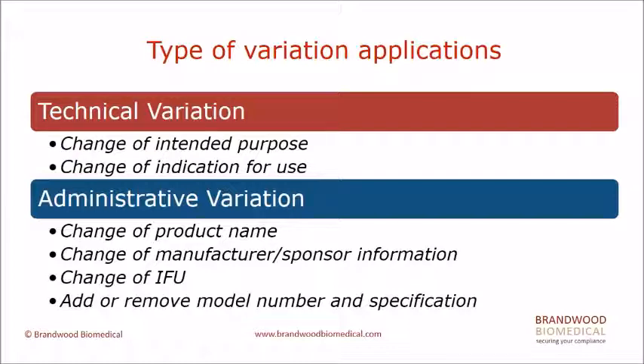The second type of variation is administrative variations: change of the product name, change of the manufacturer or sponsor information, change of the instruction for use, and adding or removing model numbers and specifications. Depending on the nature of the variation, there may be documents or reports requested during the review process. For example, if adding model numbers and specifications, the preclinical testing and the QC testing of the new model numbers will be required. If it's a change of the instruction for use, for example adding warning statements, there may be additional documents required explaining the reason for adding the warning statement.